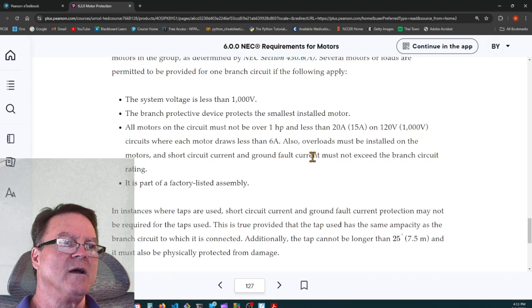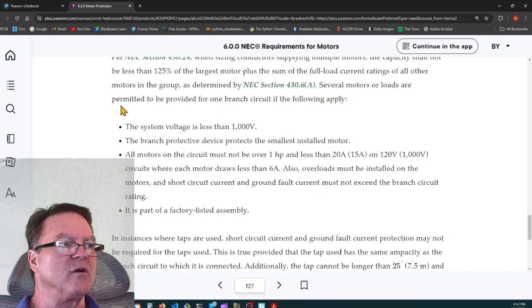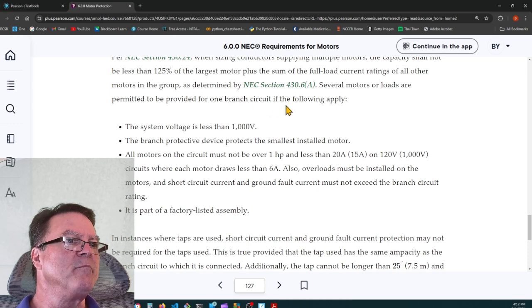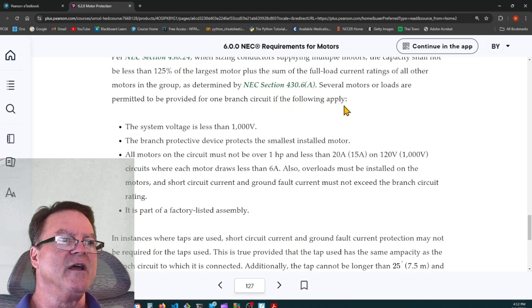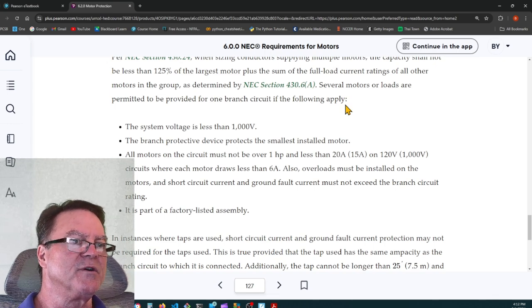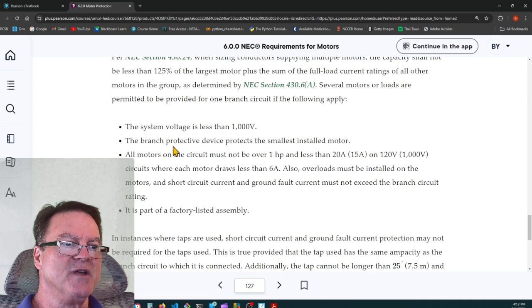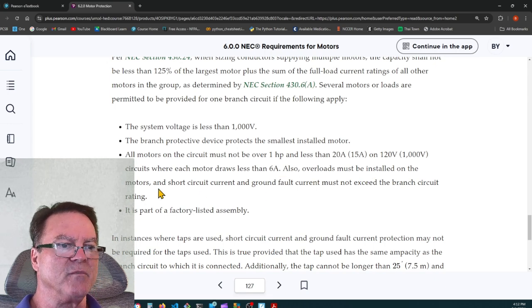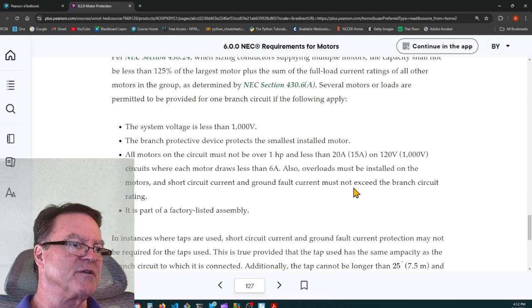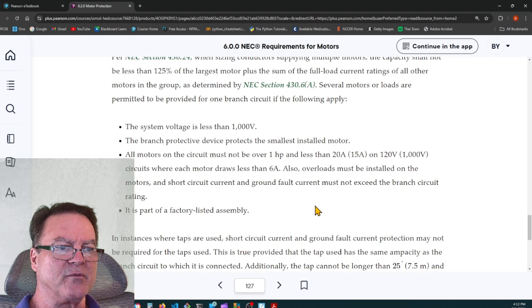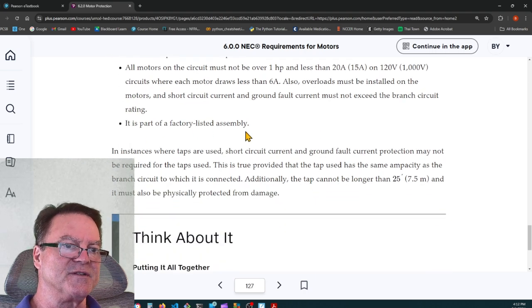All right. Let's see here. It says several motor loads are permitted to be provided from one branch circuit if all of the following apply. So you can feed more than one motor with one circuit. If the system voltage is less than 1,000 volts, the branch protective device protects the smallest installed motor. All motors on the circuit are not over a horsepower and less than 20 amps on 120 volts, or on a circuit where each motor draws less than 6 amps. Also, overloads must be installed on motors, and short circuit current and ground fault current must not exceed the branch circuit rating if it's part of a factory listed assembly.